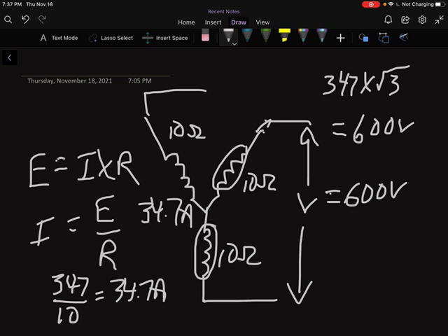So we calculated our line voltage, we've calculated our phase voltage, we've calculated our phase current. And as we talked about, if I were to put an amp clamp around that coil, I would see 34.7 amps if I could put an amp clamp around it. And if I came out into the line, we don't have multiple coils adding on or producing that current. So our current in the line would be the exact same as it would be per phase. The only thing remaining is to calculate what our power is.